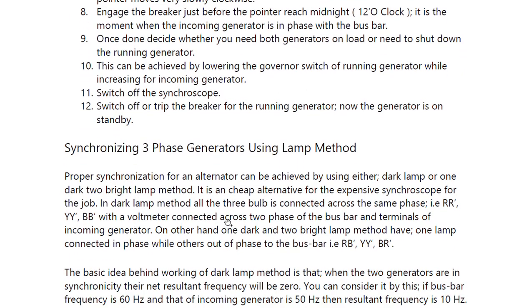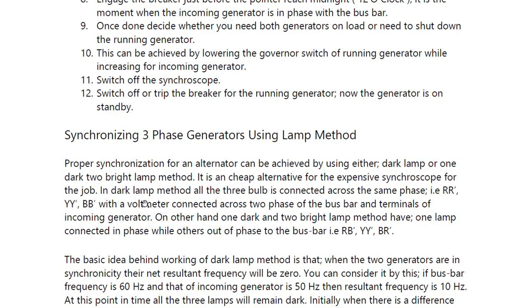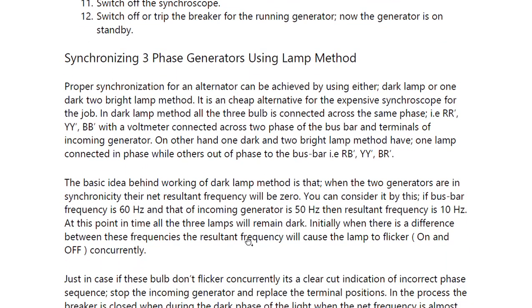Now, synchronizing a three-phase generator using the lamp method. Proper synchronization for an alternator can be achieved by using either the dark lamp or the two bright one dark lamp method. It is a cheap alternative to the expensive synchroscope. In the dark lamp method, all three bulbs are connected across the same phase — R-R, Y-Y, B-B — with a voltmeter connected across two phases of the bus bar and the terminal of the incoming generator. In the two bright one dark method, one lamp is connected in phase while the others are out of phase with the bus bar — that is, R-B, Y-Y, B-R.